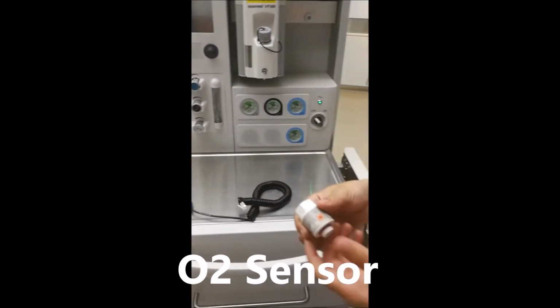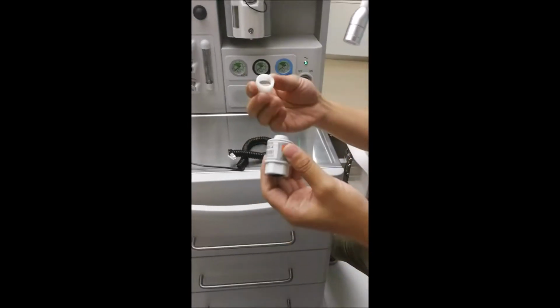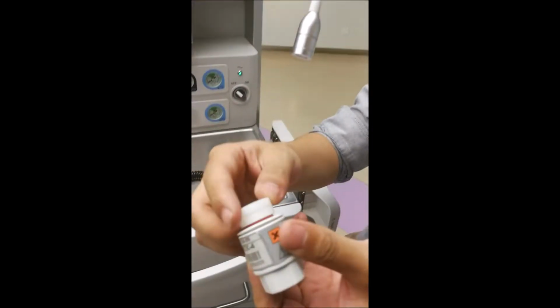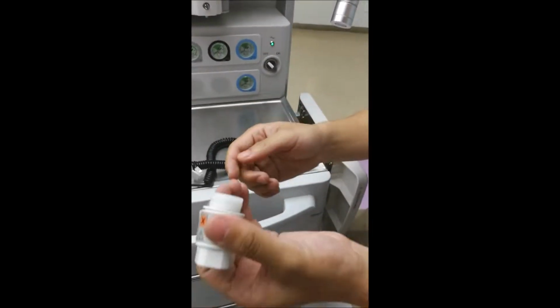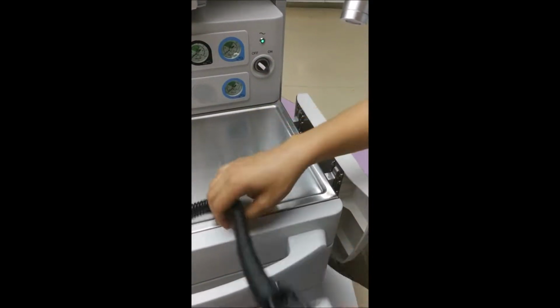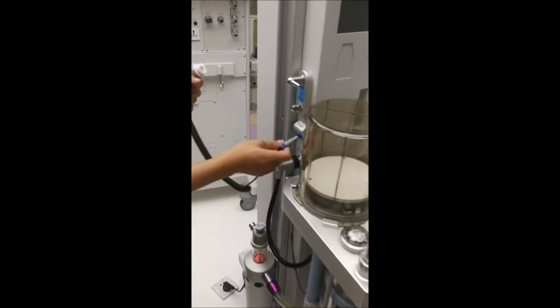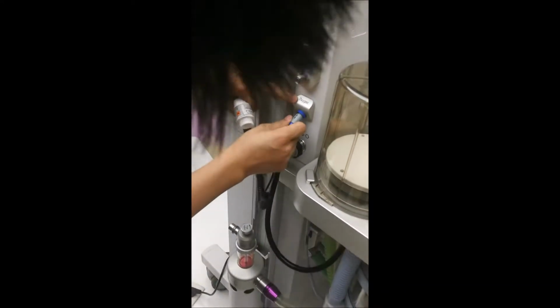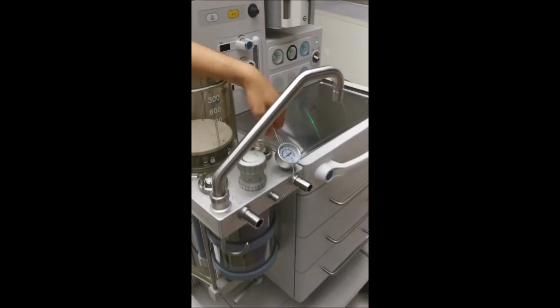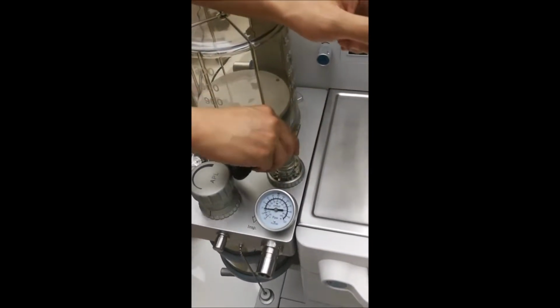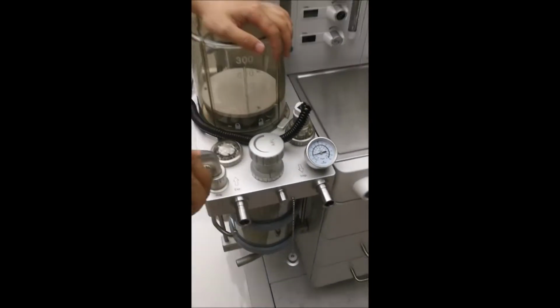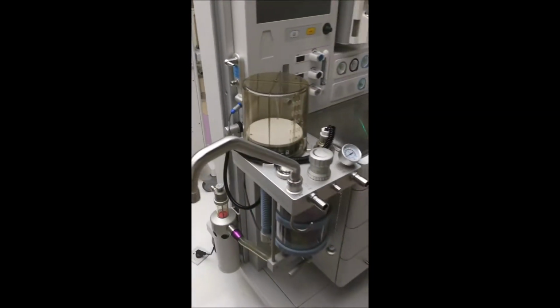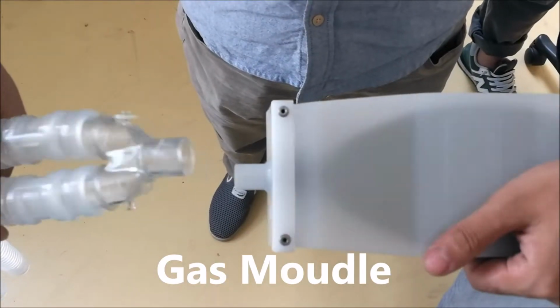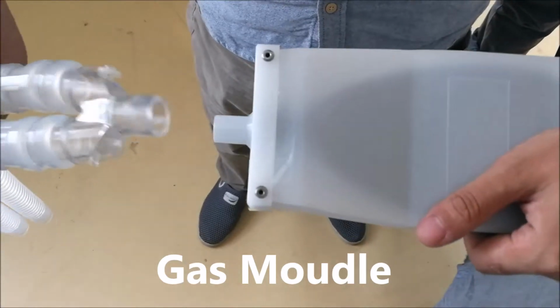Okay, this is the oxygen sensor. When we open it, we find this part and this adapter. First, we install this adapter. Okay, the second one, connect the tube. The cable. This cable side, this part we connect here, oxygen. And there's another way, we just open this part, inspiration, connect. Okay, it's finished. Oxygen sensor. Okay. Connect a mainstream gas module adapter between Y-piece and test line.